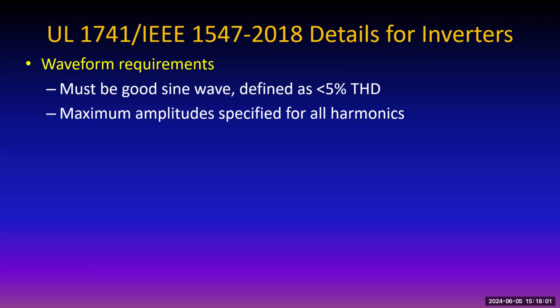All right, let's first talk about some general requirements for inverters. You have to have good waveform. If it's not a good sine wave, it kind of messes up what's on the utility line. So good sine wave is defined as less than 5% total harmonic distortion. Some of you know what that means. Not everybody does. Right now, all you need to know is it's listed to UL 1741 and it meets all these requirements.